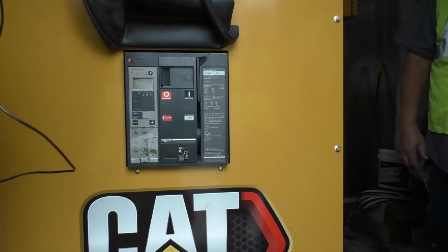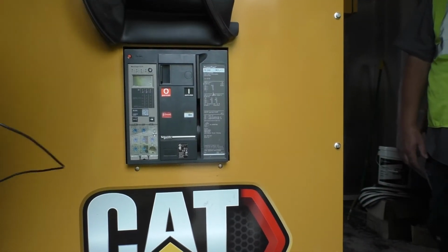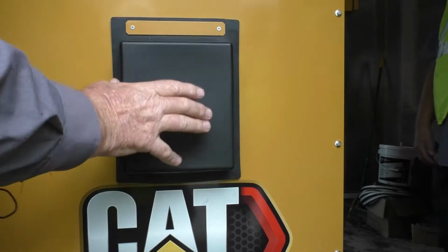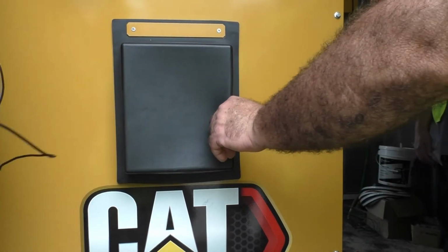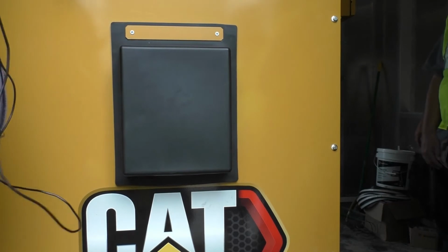Breaker's now closed. We will have lost that circuit breaker open input from the contacts on the breaker. So now if we crank it and run it, the transfer switches see power from us.